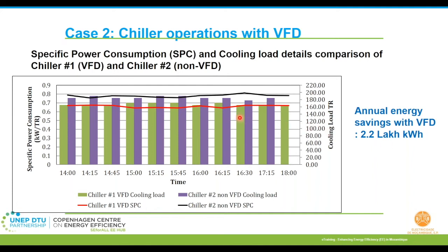Further technical details: if you look at the efficiencies, for chiller one with VFD, this red curve, the specific power consumption is low, that is, it is relatively efficient compared to the specific power consumption of chiller two. The energy consumption difference is about 2.2 lakh units on an annual basis. That is, chiller one with VFD consumes 2.2 lakh units less energy compared to the one without VFD.